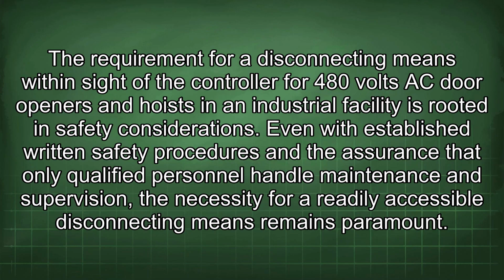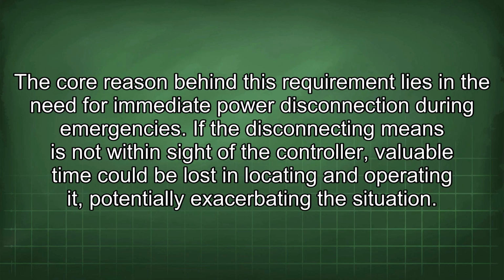The requirement for a disconnecting means within sight of the controller for 480 volts AC door openers and hoists in an industrial facility is rooted in safety considerations. Even with established written safety procedures and the assurance that only qualified personnel handle maintenance and supervision, the necessity for a readily accessible disconnecting means remains paramount. The core reason behind this requirement lies in the need for immediate power disconnection during emergencies. If the disconnecting means is not within sight of the controller, valuable time could be lost in locating and operating it, potentially exacerbating the situation.